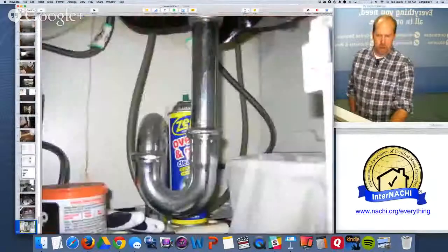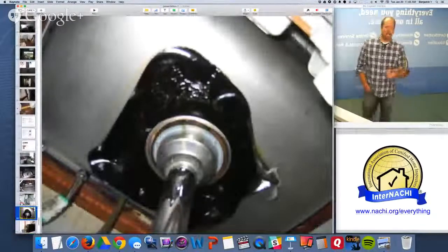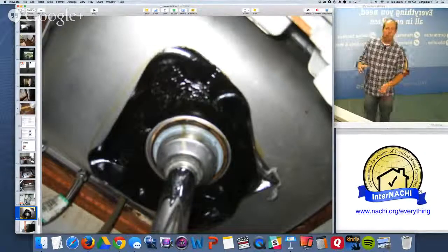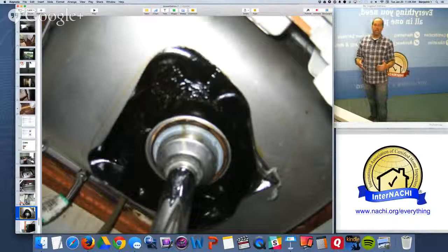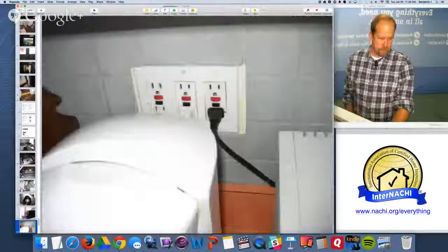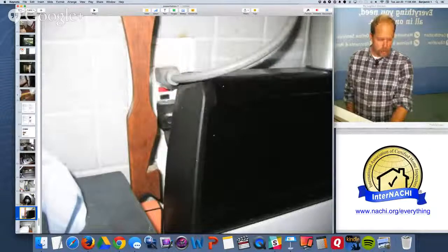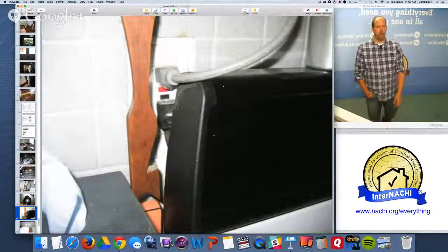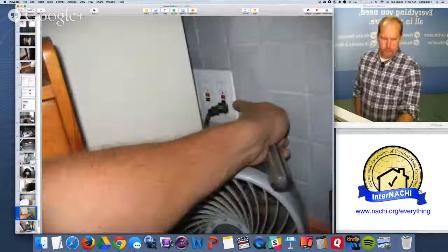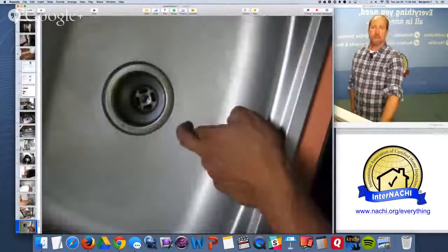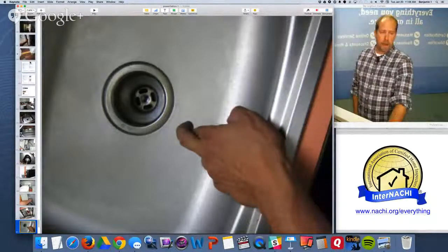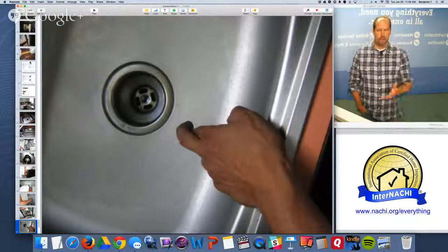Going into the kitchen: run the water — it's leaking there. Always take a picture underneath the sink; you don't know how many times I've found a sink that looks great on top but underneath the overflow has been rusting for ten years and is about to give. The ground faults here are really bad and the receptacles behind the stove — there's a lot of renovation going on but not by a professional. The refrigerator was actually plugged into a ground fault. The sink gurgles — I'm not sure why. I don't have to diagnose it; I just report the observed indications of a problem at the sink.